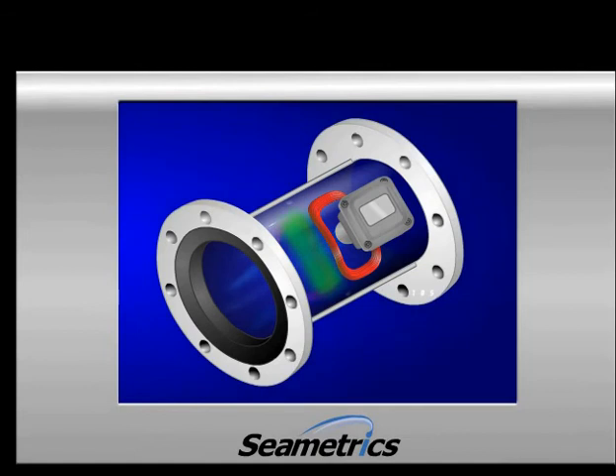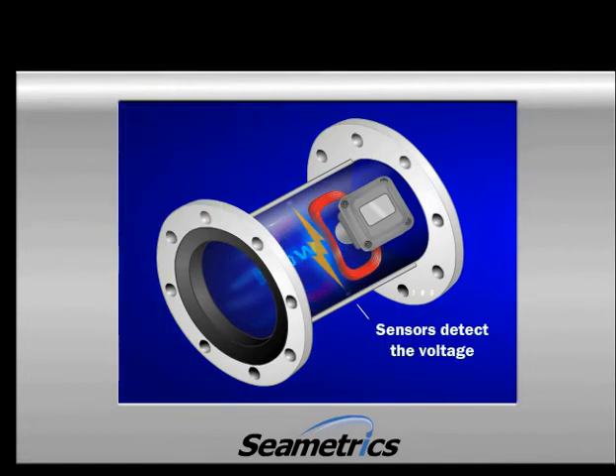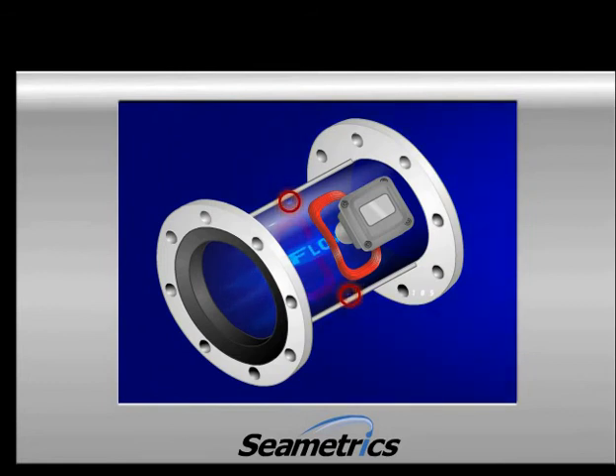The magmeter works the same way as the alternator in your car. By Faraday's law, if a conductive material, such as irrigation water, goes through a magnetic field, it creates a small voltage. If you measure that voltage and you know the size of the inside of your meter, then you can calculate how much water is flowing through your pipe.